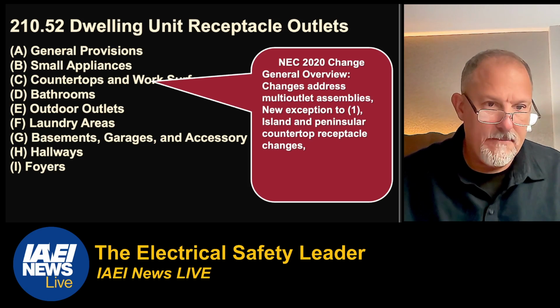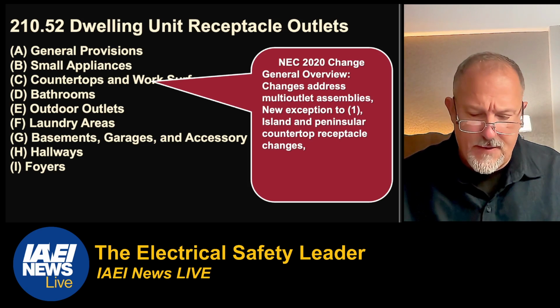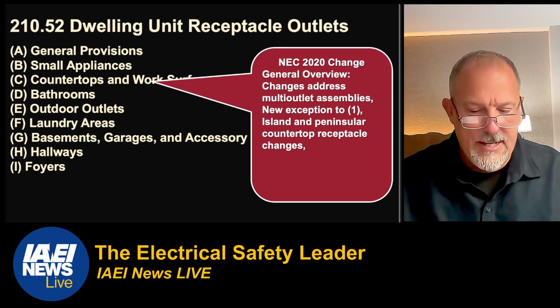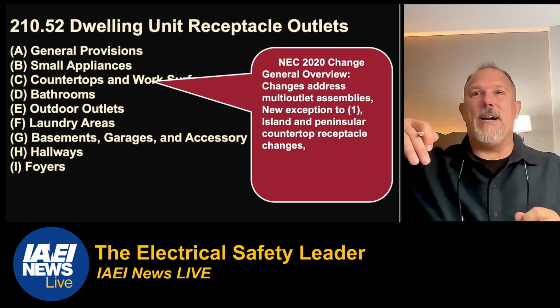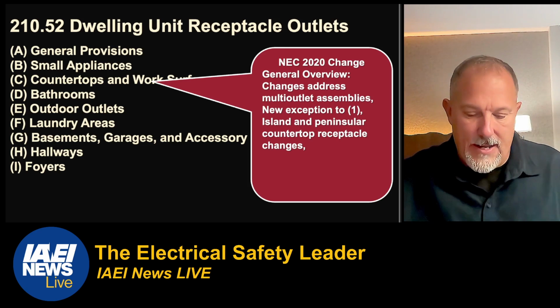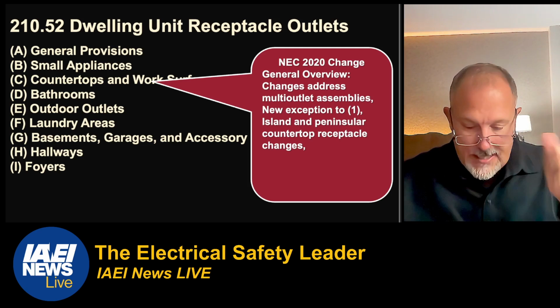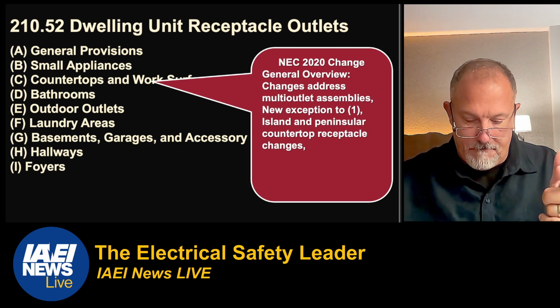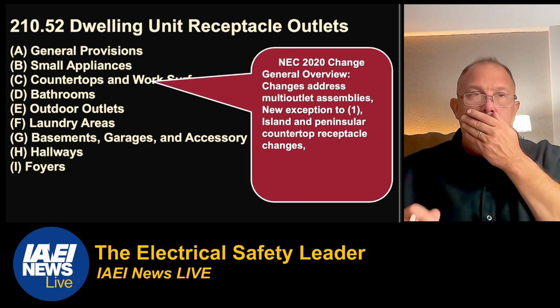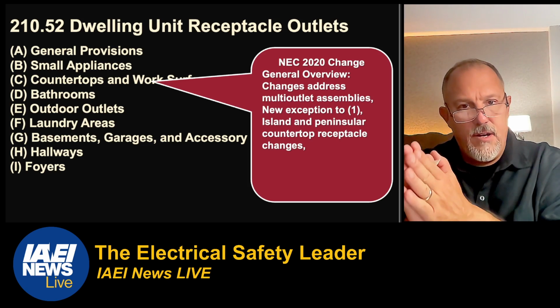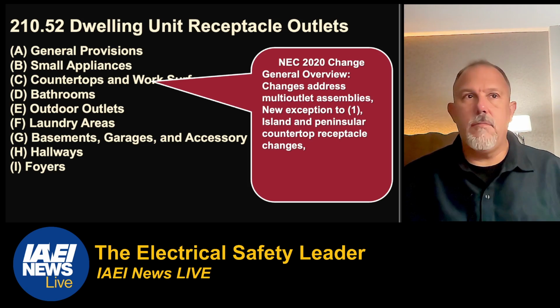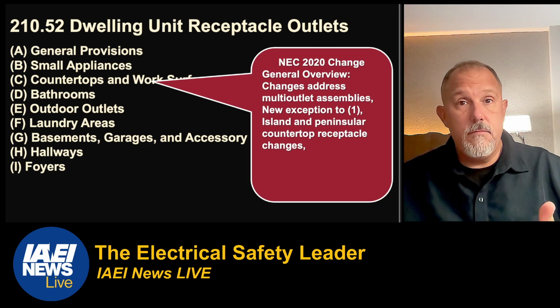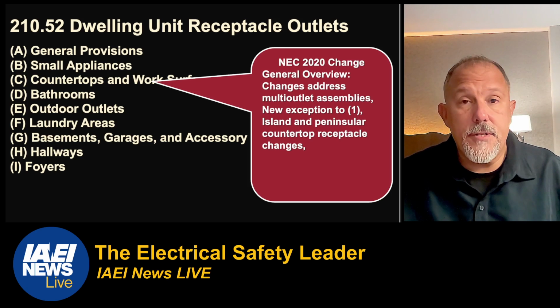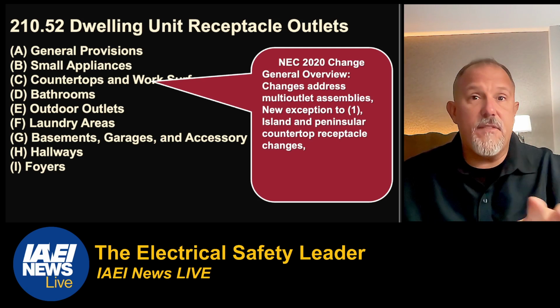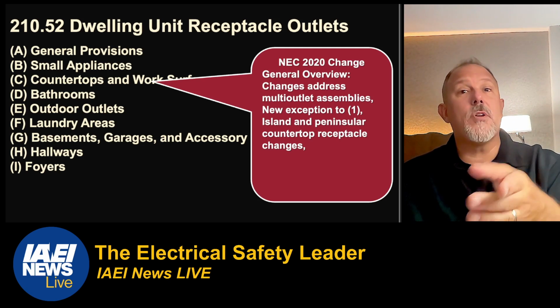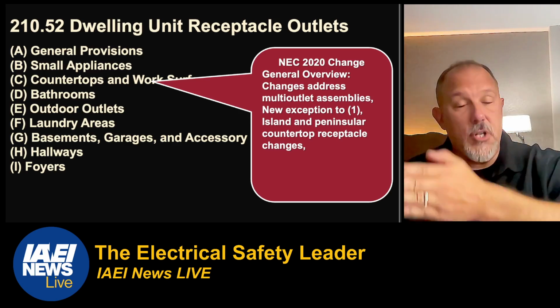We've gone through this debate. We've had the arguments of how many receptacles do we put on a peninsula or an island. We went through what's the connecting edge. In the last cycle, we went to a calculation of area, and we're trying to make life easy. Well, I'll tell you what happened. The Consumer Product Safety Commission sent us a note and shared with us data of the number of children, adults, whomever, who have pulled deep fryers, crock pots off of these locations. Why? Because the receptacle is located below the countertop and the cord drapes over the edge.